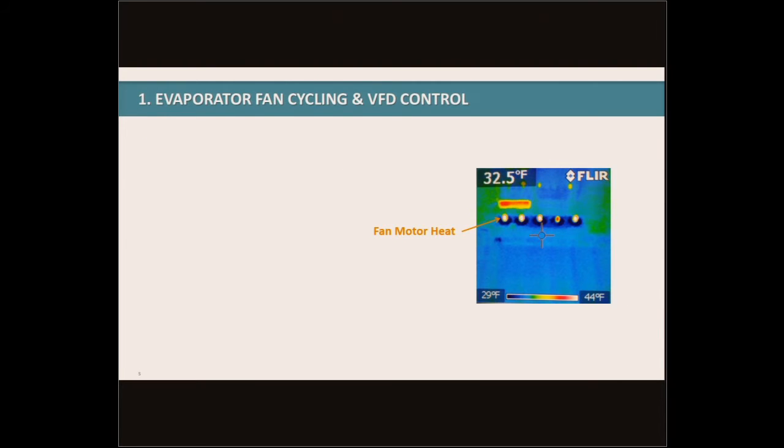The first point I want to talk about today is evaporator fan cycling and VFD control. What we want to advocate is enabling fan cycling in the control system so that the fans operate with the liquid solenoid valves. As refrigerant is needed, our liquid solenoid opens, the evaporator fans turn on, refrigeration is taking place. As the temperature is satisfied, the liquid solenoid then closes, the fans turn off, and refrigeration is done with. We do not want to keep the fans operating the entire time as it uses excess energy and also adds motor heat to the room.